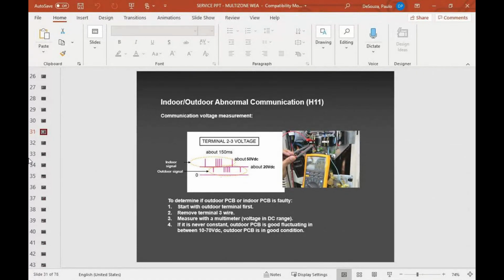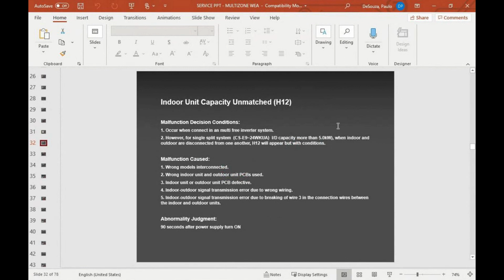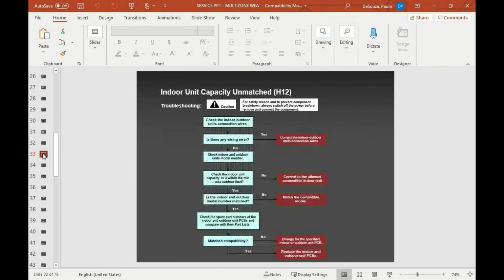Make sure it's not touching any ground or anything to cause any confusion or any short. And if you're getting fluctuating voltage, that means your outdoor PCB is in good shape. The problem is with your inside unit.